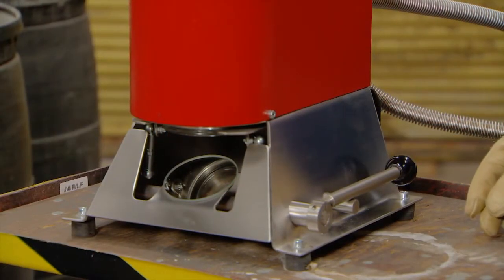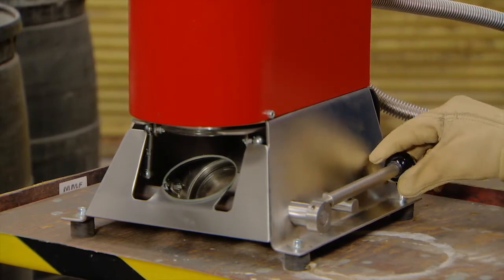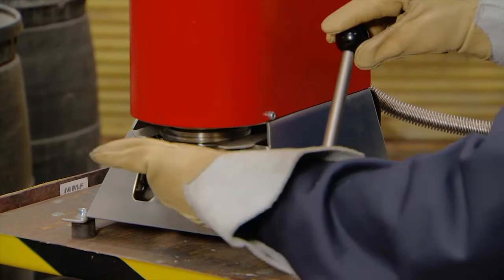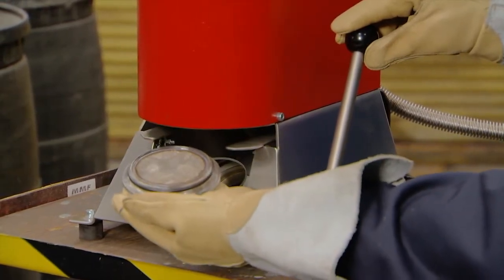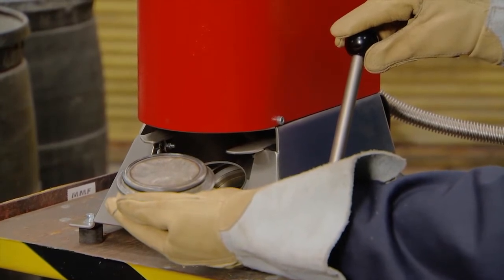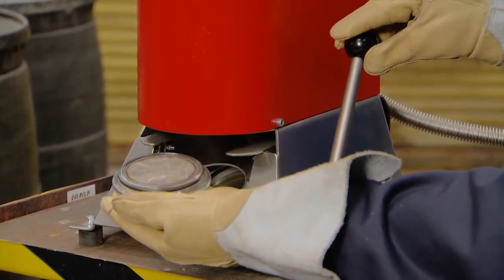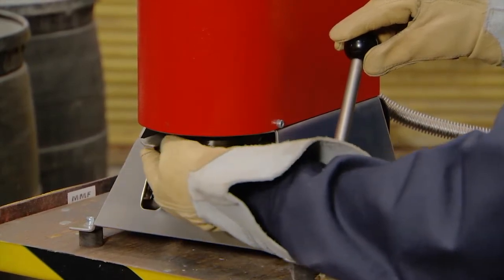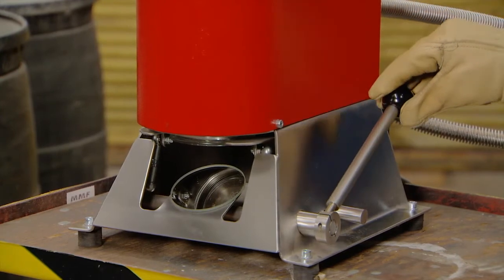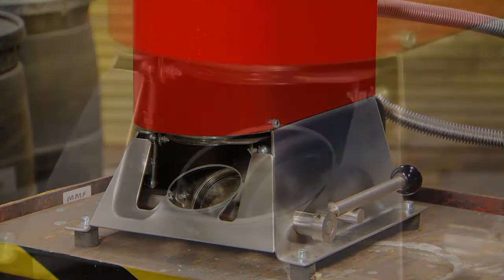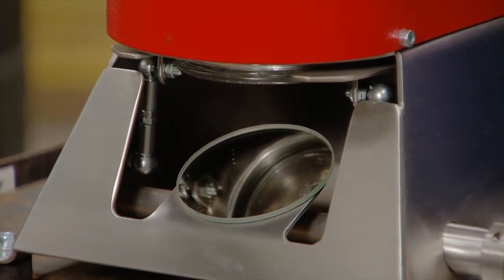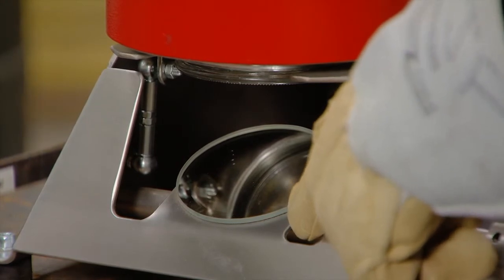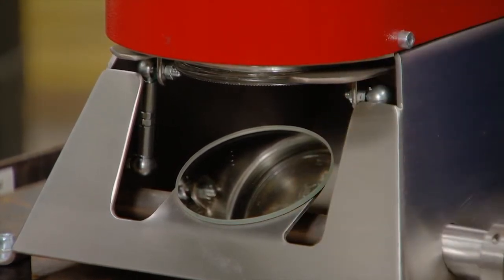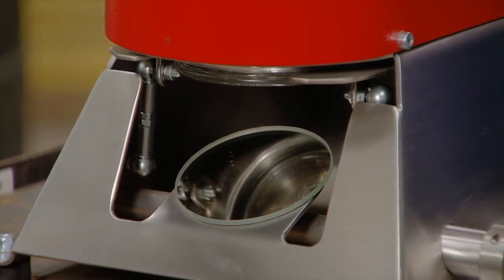When exchanging the powder, the lever should be raised using gentle force up, take out the glass, and exchange the powder. When the powder has been exchanged, put the glass back in, slide it into position, and gently lower the lever. The powder has normally a white color. When it gets moisturized and old, it changes color to purple. This can be seen using the mirror and watching the color change of the powder. This should be done on a daily basis during operation and before every operation.